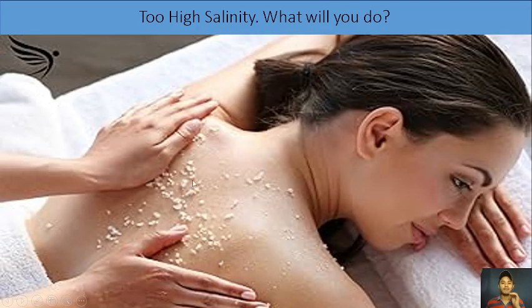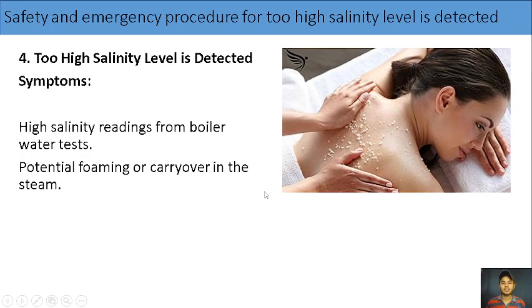Okay, next, we have too high salinity. What will you do? So when the salt is like that, what will you do, right? Okay, so let's go. Symptoms of too high salinity level in our boiler water. First, we have high salinity readings from boiler water tests. So we will have to take a sample and test the water sample of the boiler if the salinity is high or it's normal. So potential foaming or carryover in the steam.